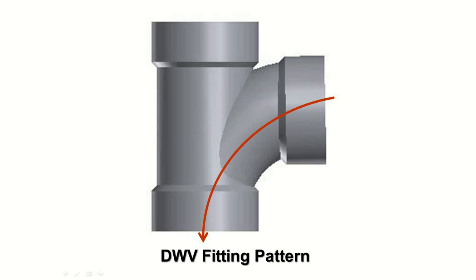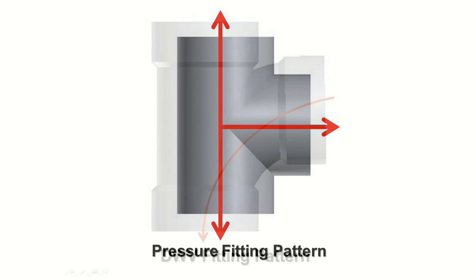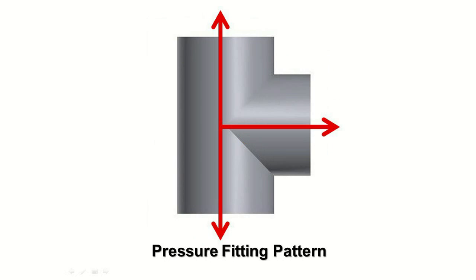Remember, DWV fittings rely on gravity and the flow pattern to move the effluents downstream. Pressure fittings can only be used in conjunction with pressurized pipe. If these types of fittings are inadvertently used with a non-pressure system, clogs may occur because there is no flow sweep in the pattern.